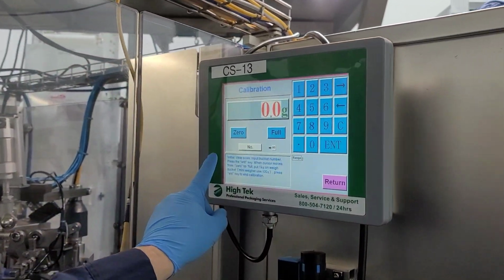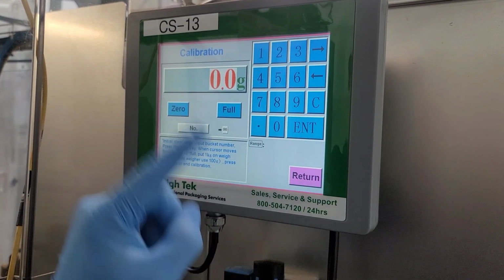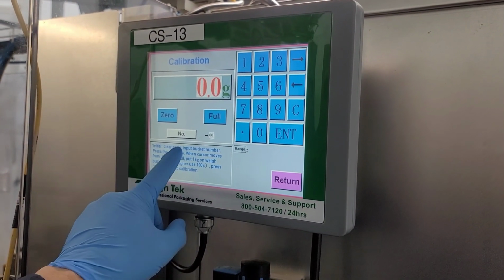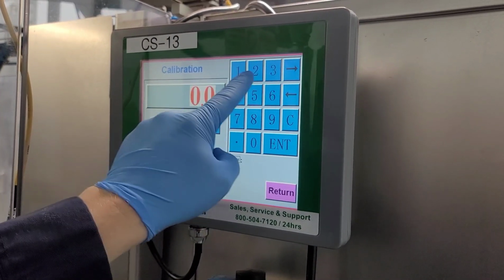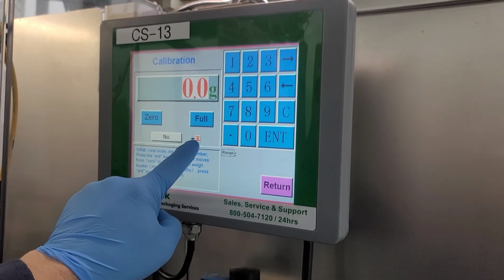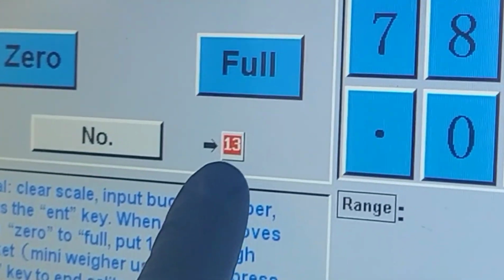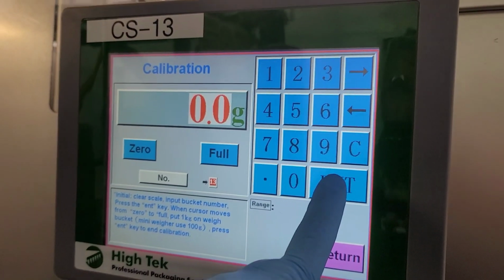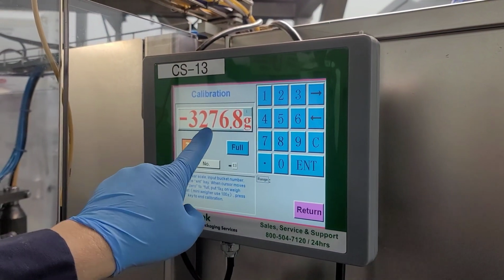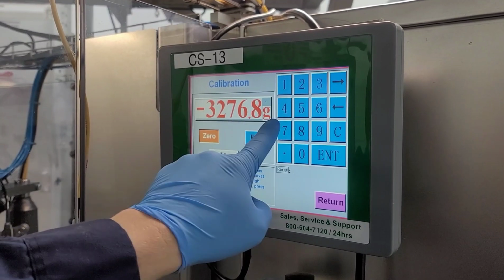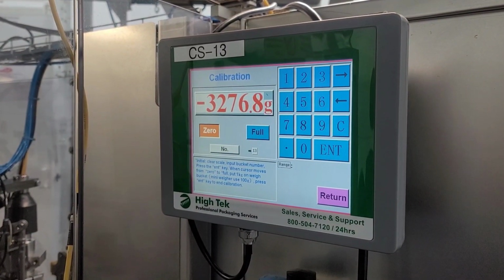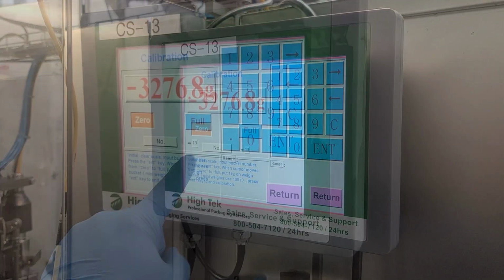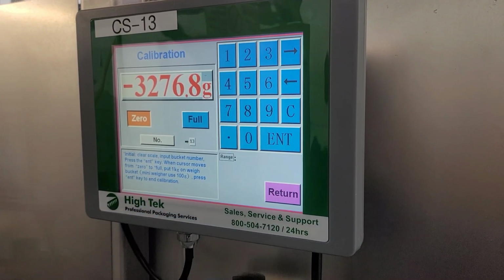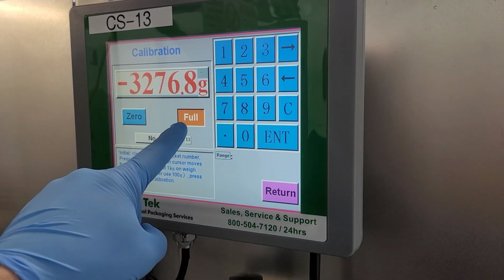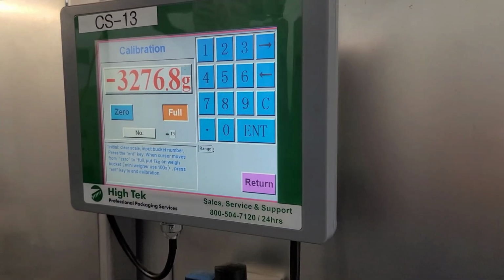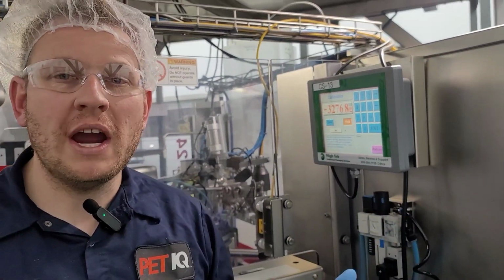The first step is to select the bucket. We want to clear the scale, which we cleared bucket 13, and we're going to input the bucket number. 1, 3. You can see right here the bucket number has been highlighted from our input, and we will push enter. You can see the same number is reflected here as was on the manual operation that we were previously in. Press enter once more and see the cursor move to full. At this point, it is now ready to place the calibration weight in the bucket.